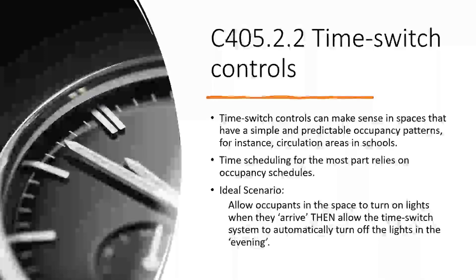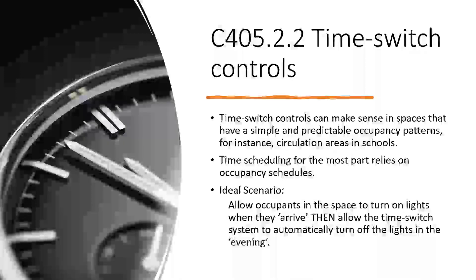Time scheduling for the most part relies on occupancy schedules. One reason it's becoming less efficient is because buildings are becoming more diverse with multiple uses and space types, making occupancy patterns harder to predict — and we can't easily set all those schedules. Buildings are also renovated over time, changing their space types. The ideal scenario is that lights turn on when occupants arrive and are set to an evening time to turn off automatically when everyone leaves. The problem is you can't forget about janitorial, maintenance, and other personnel who operate before everyone gets in and after everyone goes home. Operating hours are actually longer, but we can reduce and only light the parts that are needed.